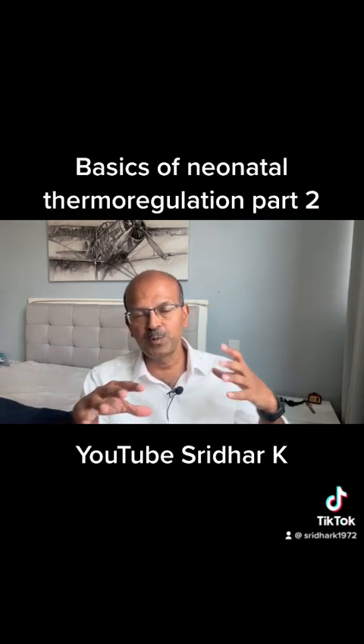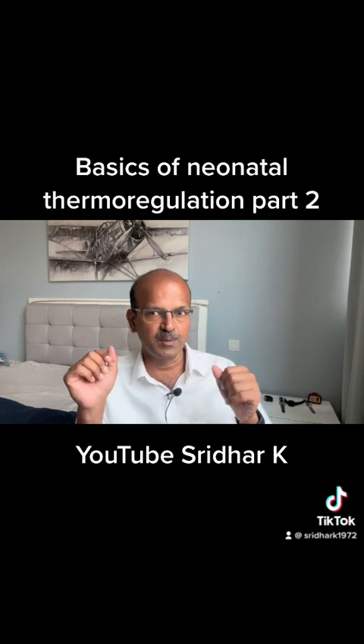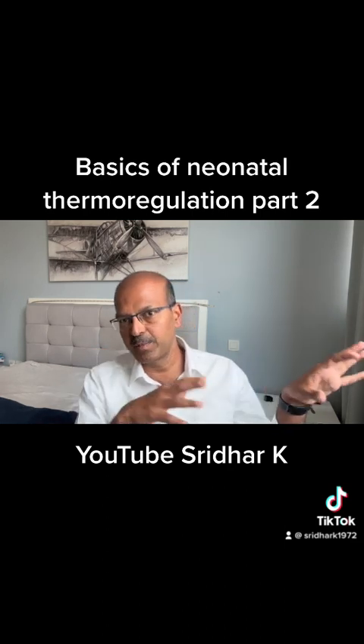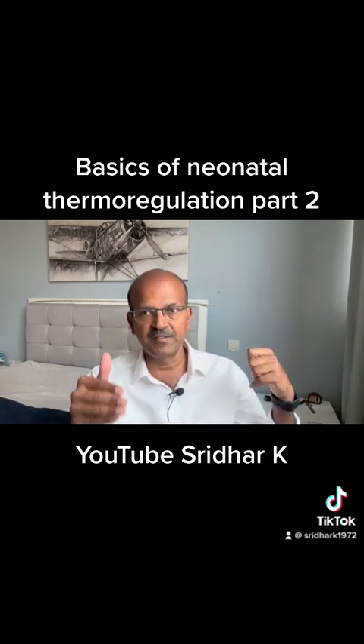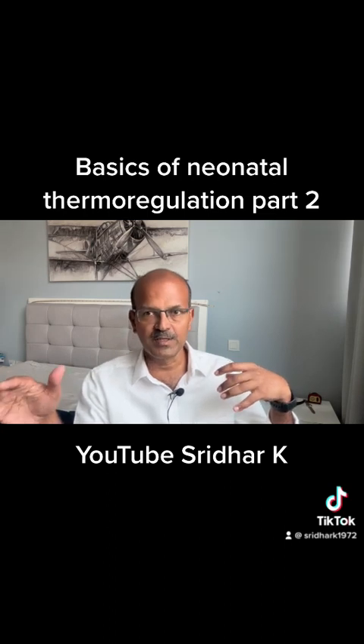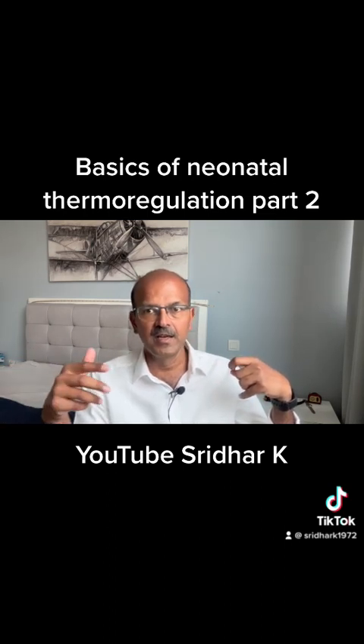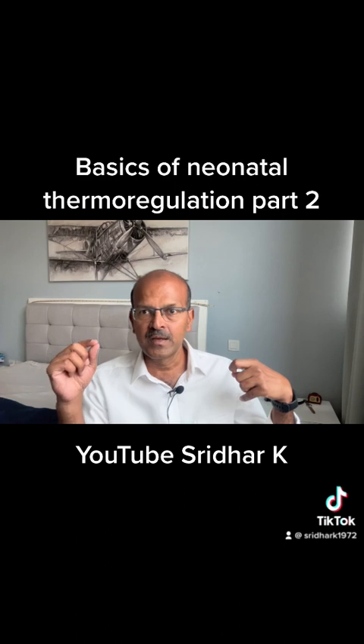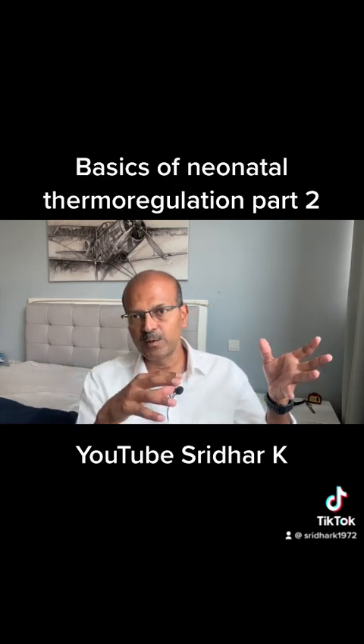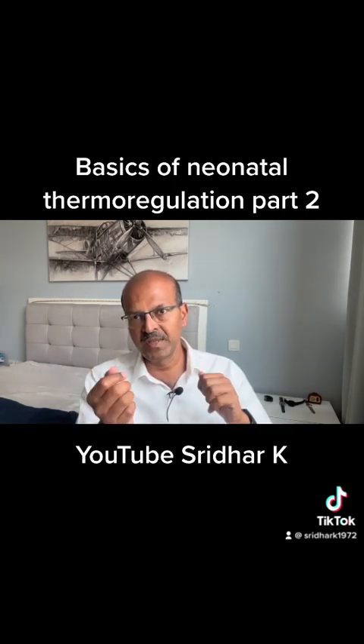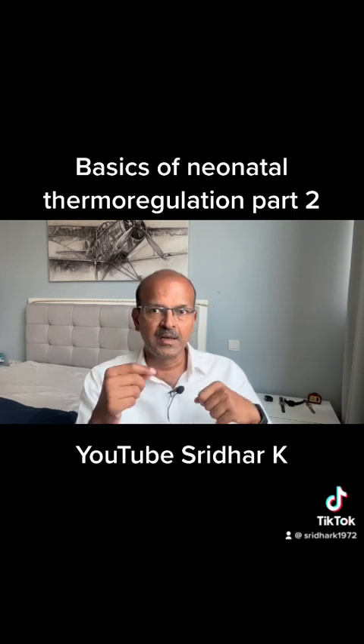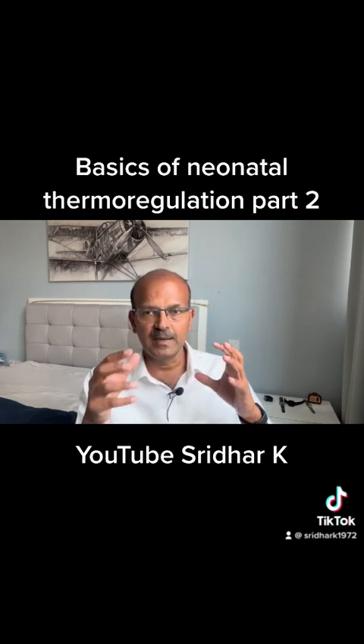The modes on the incubator, again, it's similar, though you don't have the pre-warm mode. When you are keeping the incubator ready, you usually keep it at 35 to 37, so closer to 37 for the smaller babies when you're planning to receive a premature baby in the unit. There are modes which include manual mode and the servo mode. Manual is also called the air mode, and here basically you're setting the required air temperature.